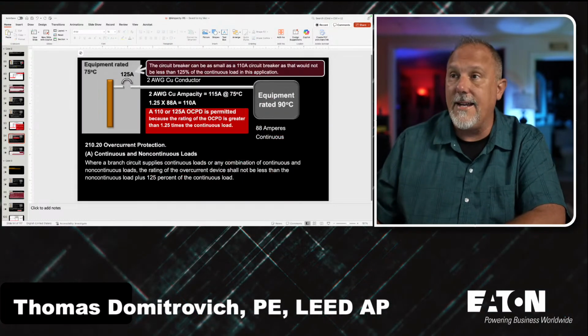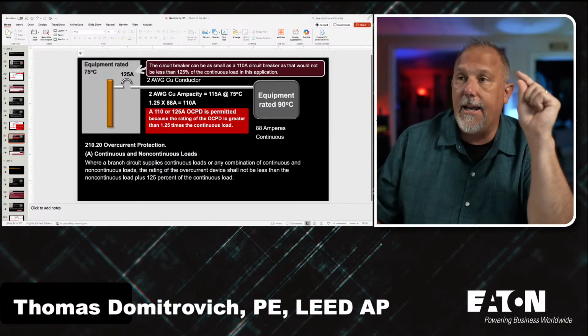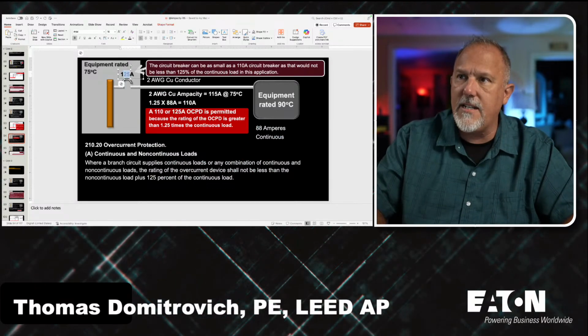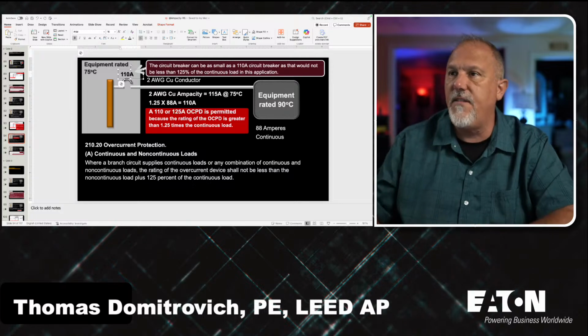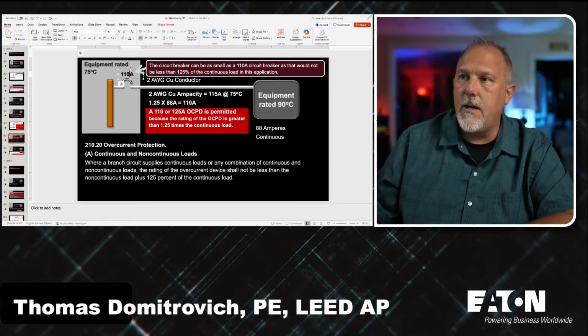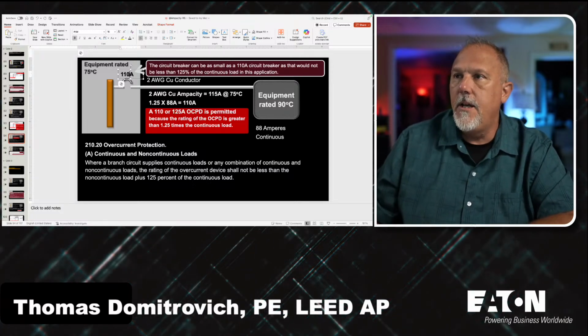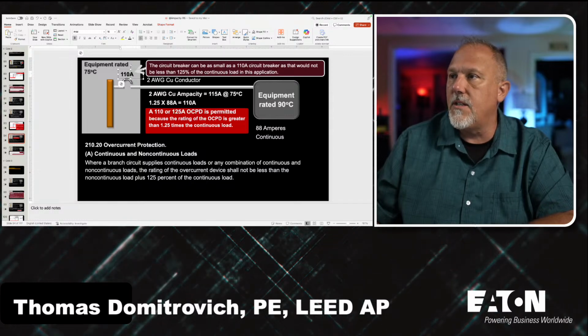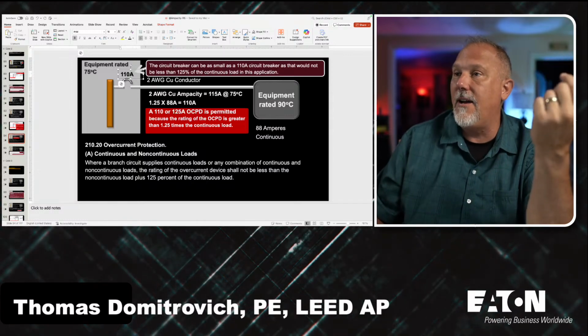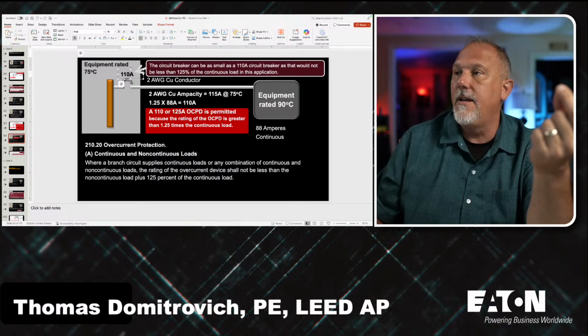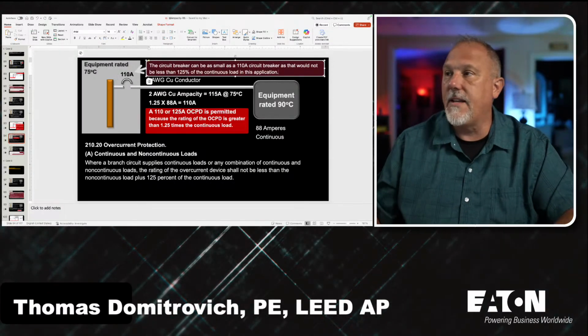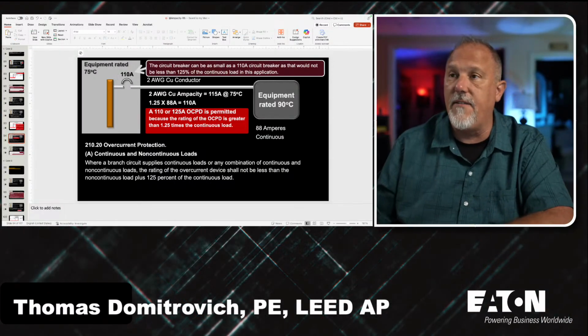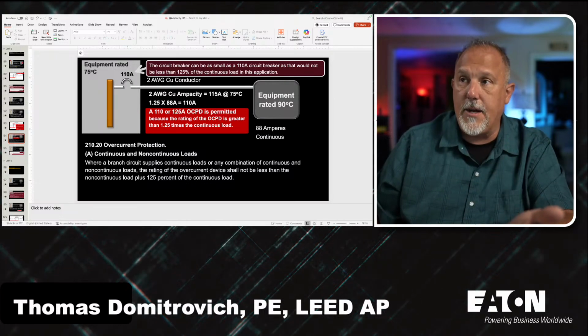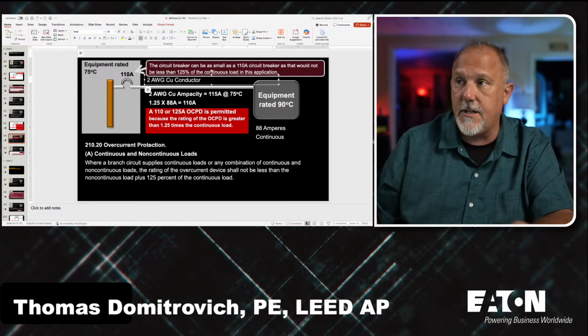So if I come down to the next slide, I say I'm going to put 110. Why would I spend money on a 125 amp breaker when I can just do a 110 amp breaker? This circuit breaker can be as small as a 110 amp breaker that would not be less than 125%. All right, perfect. And it can be as great as 125 amp. So I put a 110 amp breaker. I got a 2-gauge copper conductor.